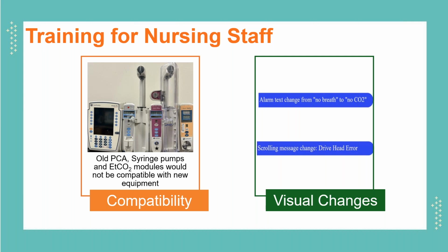So the alarm text change was going to go from no breath to no CO2. And then there was going to be a scrolling message change. Instead of a general occlusion error, it's now going to say drive head error, so that they could communicate with the new ones. I guess they didn't want to actually flash these new ones just because they were going to be replacing them all at the same time. So there was just going to be that few weeks of compatibility issues where the clinical team couldn't use the old ones with the new ones, and hopefully we'll get those out of the way as quickly as possible.